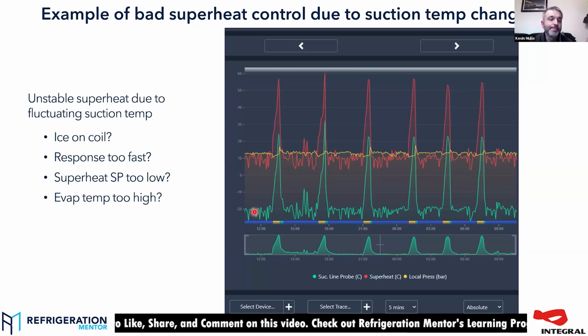One of the other ones is response time. RDM gives you, for valve control, response on and response off. That is a global parameter for how fast the valve reacts to a change in superheat. They've done that, I think, because, let's put cards on the table, not that many people truly understand, if you've got P, I, and D, what all those things do. There's a whole group of people who specialize in just tuning PID algorithms. So people tend to fiddle with the numbers and see if it makes a good thing or a bad thing a lot of the time. Yeah, RDM simplified that for you. You can have a response on, a response off, and you can have between 0 and 30 for how fast you want that response to be on this particular type of valve.